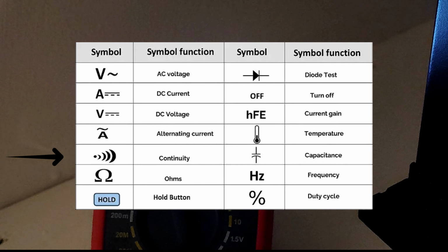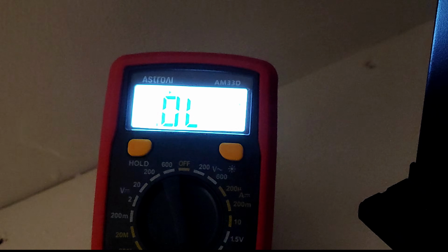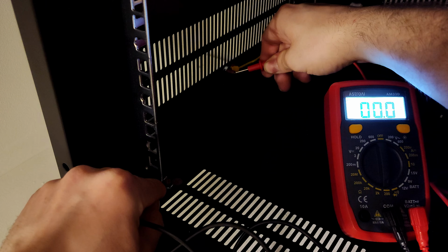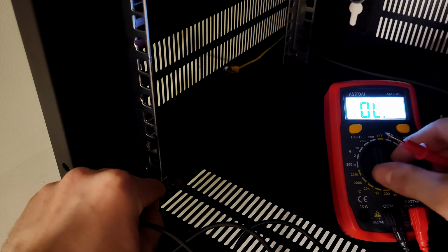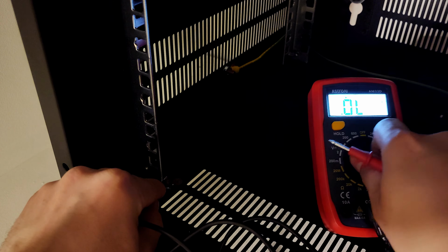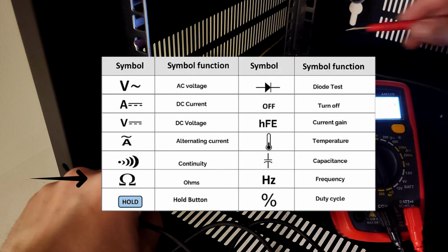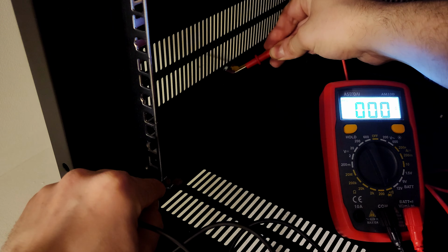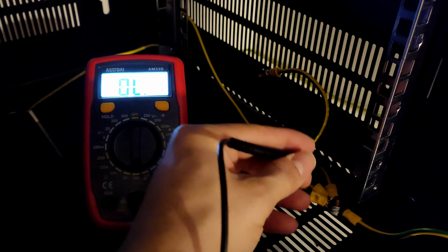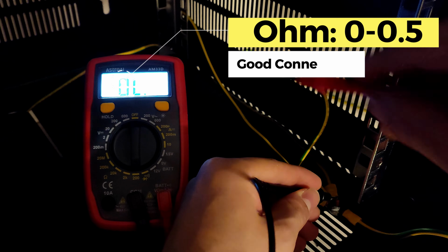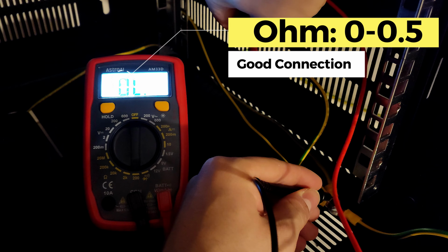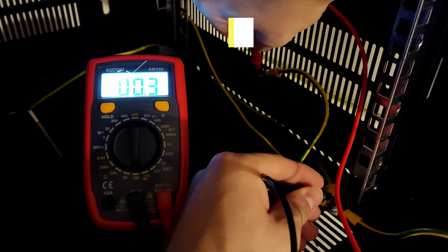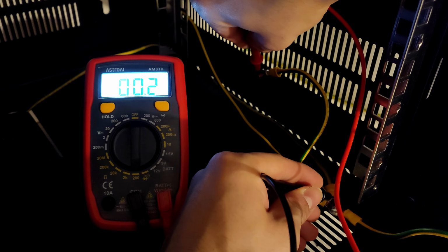To have proper grounding, we have to check its continuity using a multimeter. First, you set your multimeter to continuity mode. If your meter lacks a dedicated continuity setting, you can use a resistance mode, which is the ohm mode. A reading close to 0 ohm indicates a strong, low resistance connection. For instance, a reading between 0 and 0.5 ohms is ideal. Anything significantly higher suggests a poor connection.